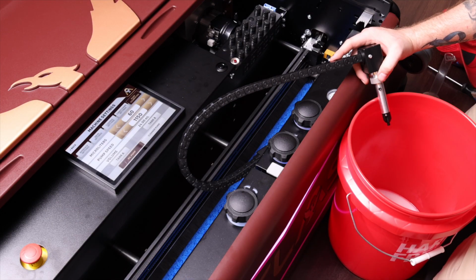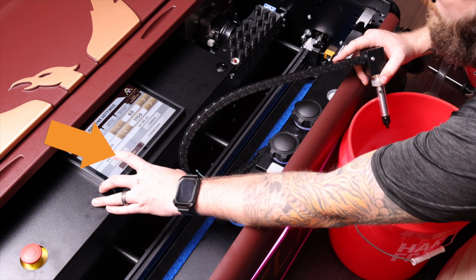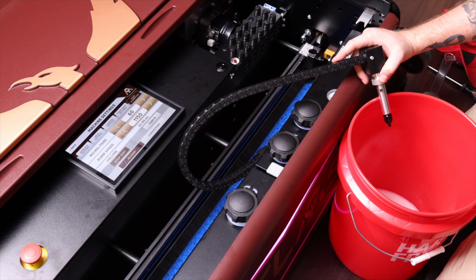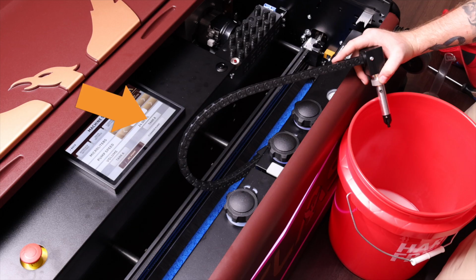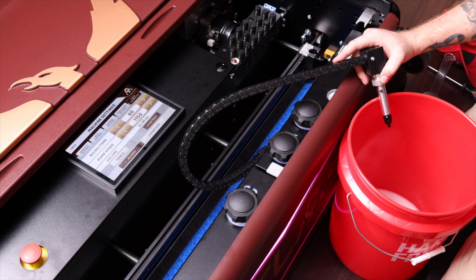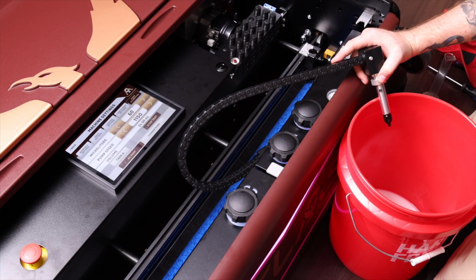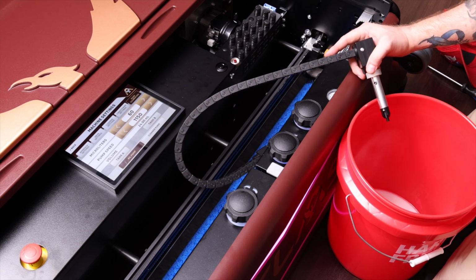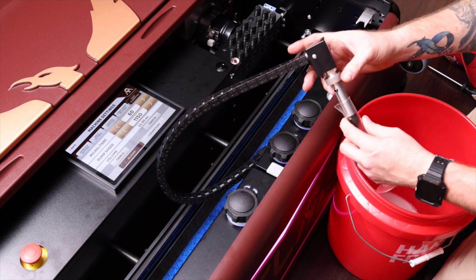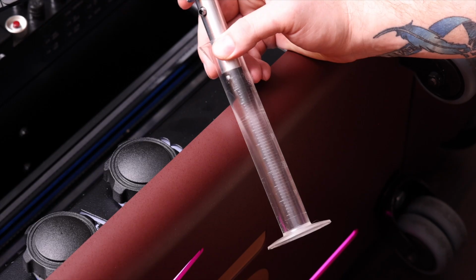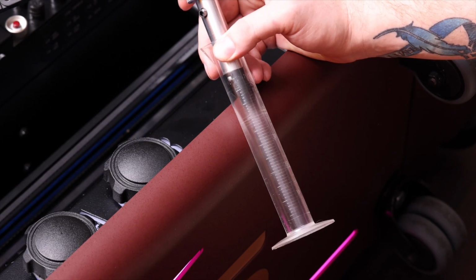Before running the calibration, we will run a quick test to push any excessive air out of the lines. On the screen, test per tank, first starting with Tank A. After a short delay, the head will begin. Once complete, we will do the same thing for Tank B. With the lines purged, we will now place the tip into our graduated cylinder. With the tip now in the cylinder, we will now run a test for each tank.